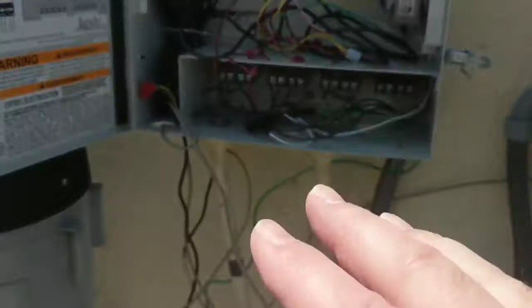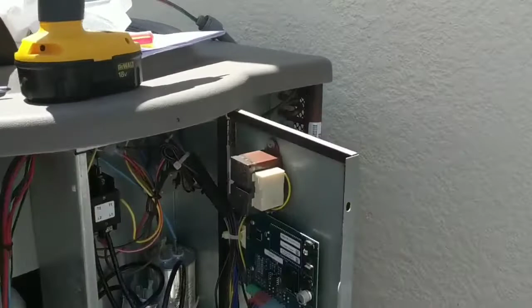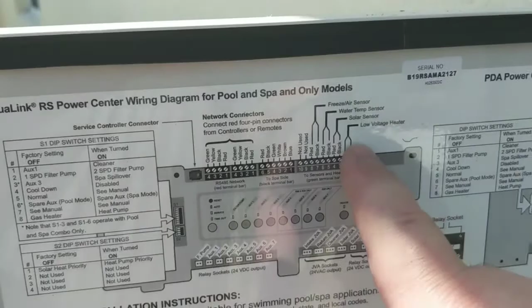What I did is I called the manufacturer. Originally I thought you have your relays in here, and the power is supposed to run through the relay to cut the heater on and off. But I've been concerned since beginning this install that this relay couldn't handle 240 volts, 60 amps running through it, which is correct. What we have is two little connectors on here that are low voltage connectors, and those go into the control board - I'll show you the connection as we get closer to starting this guy up. Basically here you see low voltage heater, pins 1 and 2 on the board. That's what we're going to end up doing.